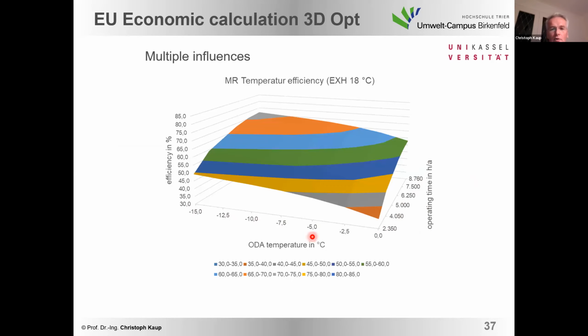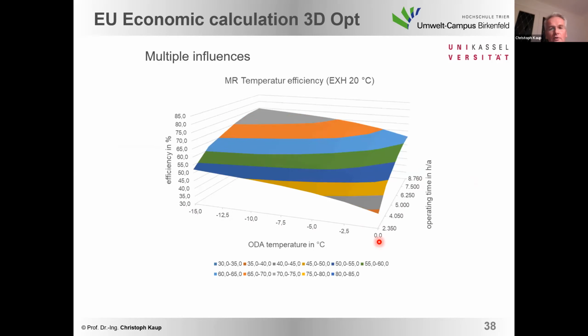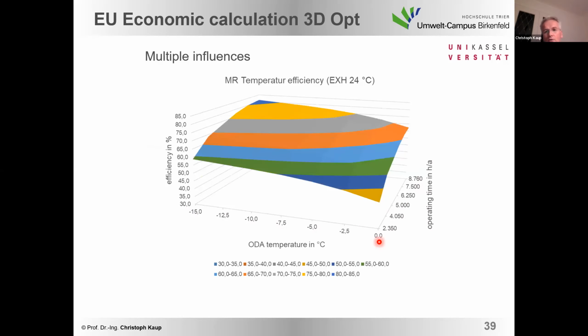Here we have the outdoor air temperature during the winter time, and we did these calculations for several exhaust air temperatures, and you see the plane which is given by all these three influence factors. That means, for example, here with 24 degrees extract air temperature in the southern parts, an efficiency of 45% would make sense, but in the northern part with the full operating time, we are going over 80%.